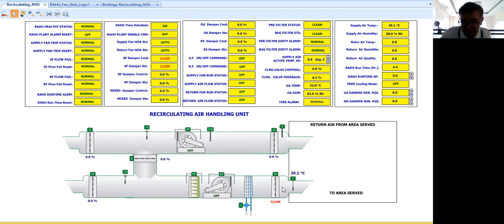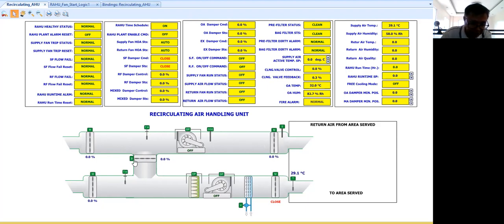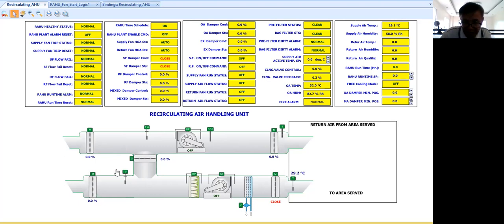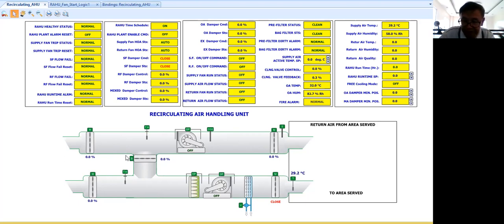When I say modulating type, this damper will open from zero to 100% open. So because in the sequence of operation that I'm trying to follow, there will be a free cooling mode.